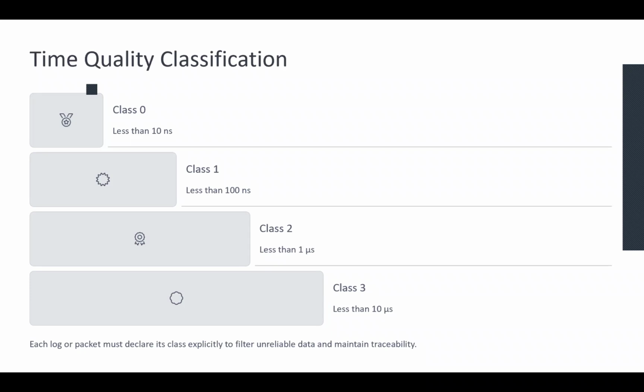Now class 3 is when we have errors up to 10 microseconds. This is an entry level synchronization quality. So every synchronization system should pass class 3. If it passes class 2, 1, or 0, it has more precise, better performance, but class 3 is the bare minimum. So it's normally used for SNTP based systems or legacy networks, where monitoring applications are not critical. It is not acceptable for closed loop control or phase dependent calculations, but might be sufficient for data archival, low rate telemetry, or delayed alarms.